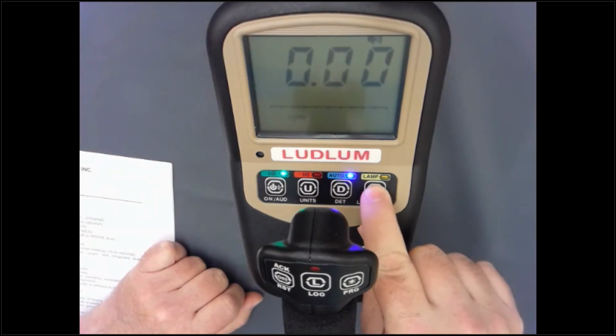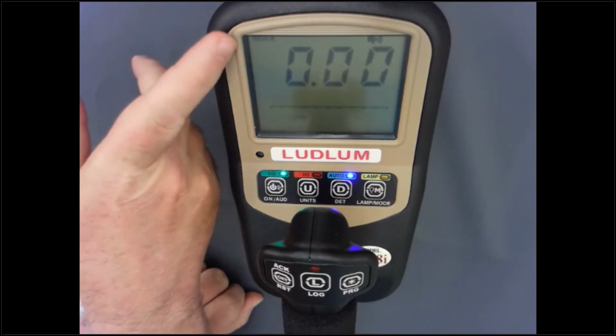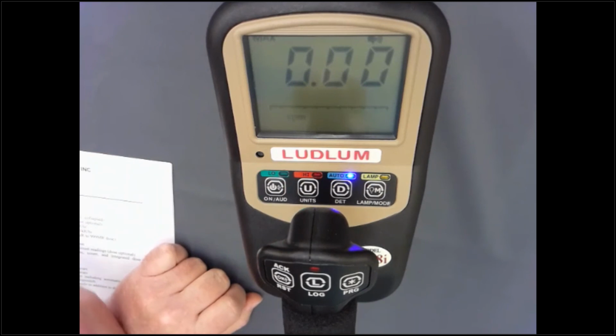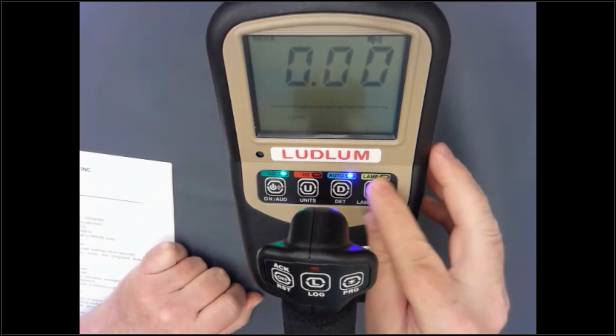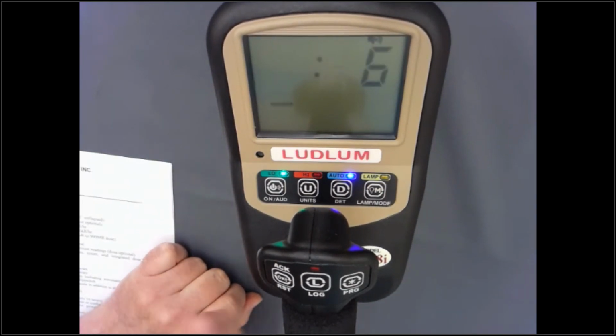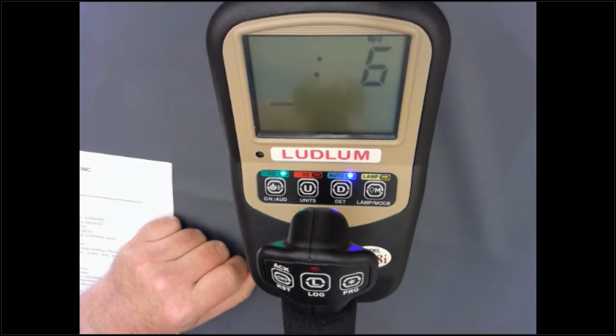As I press the mode button, we now go to a max mode, and when we're in max mode, this is going to indicate the maximum reading that you're going to read while you're in this mode. Another press is going to take it to the scaler, and in this particular case, it's set up right now as the user-defined value of 6 seconds, and it's currently in counts per minute as in counts as was indicated by the C when you first entered it. We can change the units back over to R, and it's going to give us a dose reading for approximately 6 seconds. The 6 is programmable. The user can define the length of time that they want to have one particular count for, or they can take advantage of using the built-in count timers by pressing the log button and holding it for 2 seconds, 3 clicks.